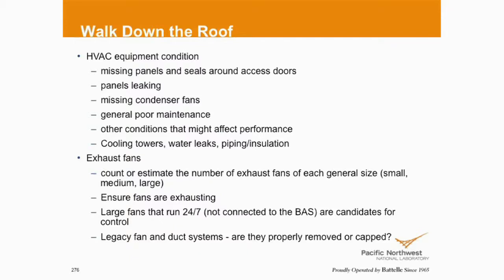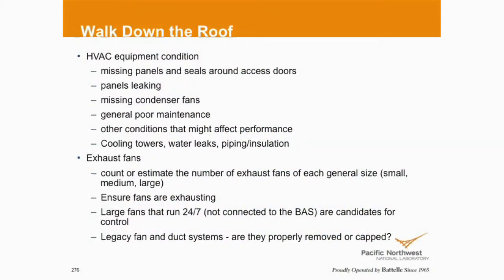Condenser fans, if it's an air-cooled chiller or rooftop unit, it failed. Guy went up there, yeah, it failed, pulled it off, didn't replace it. So now I've got a cooling system that's only got half of its capacity because I executed the remove part, but I didn't execute the replace part. How's my maintenance going on? Coils and filters can be problematic. Cooling towers, water leaks, insulation that's been, because I'm walking across piping or just the nature of the beast, I've got to remove insulation to replace the valve or fix the leak. Did I put the insulation back on? A lot of times the answer is no.